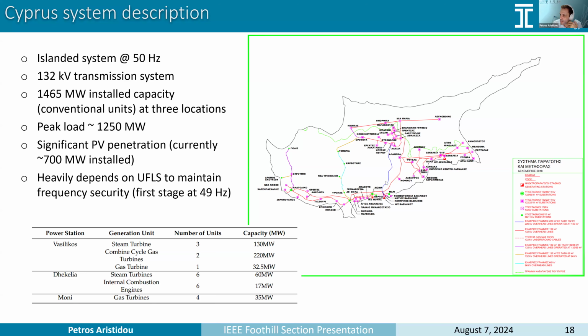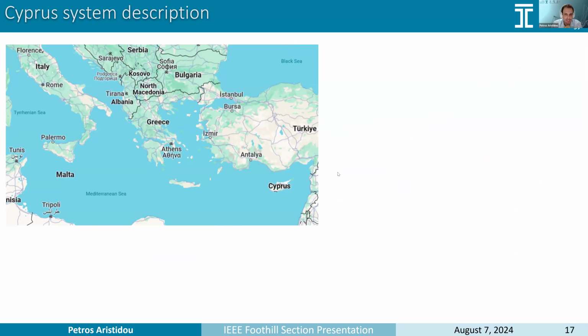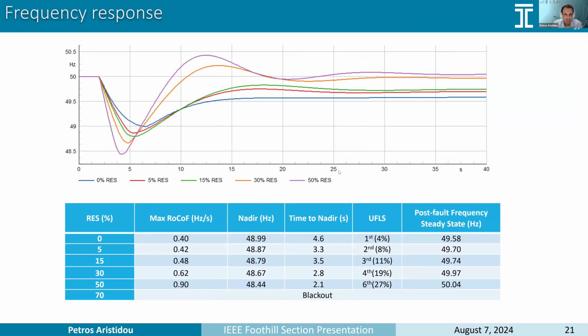Would you explain why there is an overshoot in the frequency? That's a very nice question, and it was also strange for me to see it in the beginning. That's due to the under frequency load shedding. As you can see here, in the case of 50%, it disconnects 27% of the load, because we breach 49 hertz, where under frequency load shedding starts. So that's the first stage.